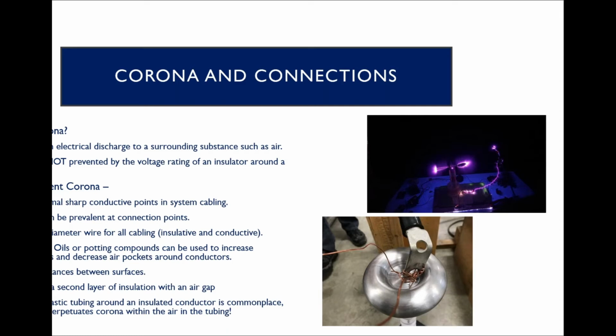You can also increase the diameter by using insulative oils or a potting compound around your cabling to really give a smooth outer shell to your entire thing. The big issue with that is sometimes this introduces air pockets, so it has to be done properly, either with vacuum impregnation or just an appropriate method in order to keep those air pockets out, which would then exacerbate the corona effect within the cable. Another goal will be to increase the distances, increase the gaps between surfaces. These can be conductive surfaces or even non-conductive surfaces, as voltages will be more likely to generate corona if there's a source for it to also have a potential to flash over to.